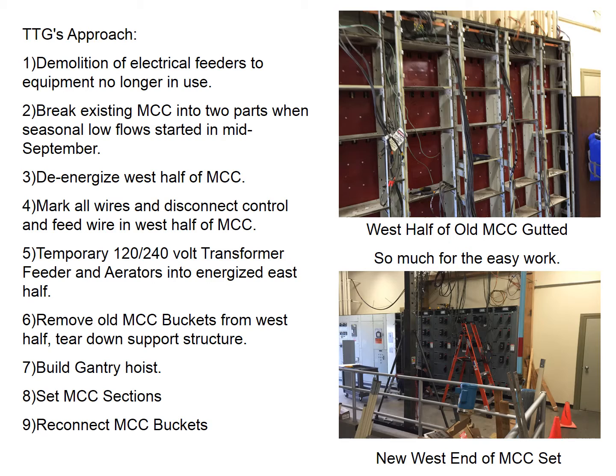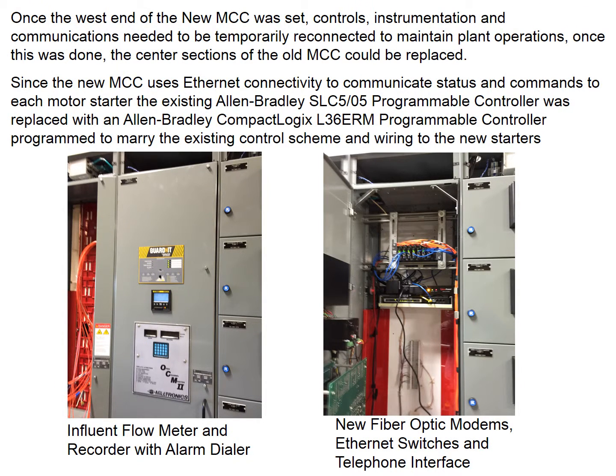Number 7, build a gantry hoist. Number 8, set the MCC sections. Number 9, reconnect the MCC buckets. So much for the easy work. Once the west end of the new MCC was set, controls and instrumentation and communications needed to be temporarily reconnected to maintain plant operations. Once this was done, the center sections of the old MCC could be replaced.